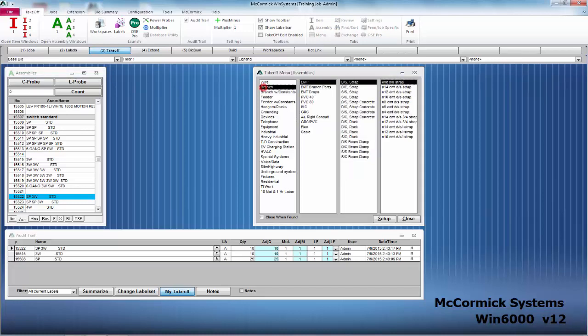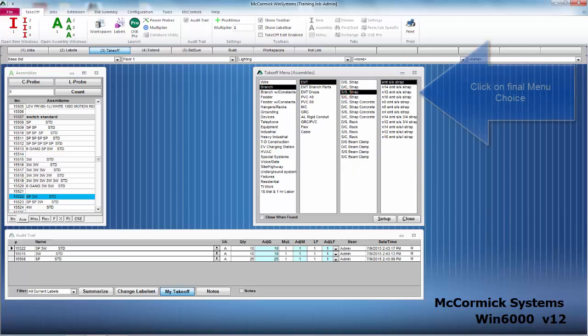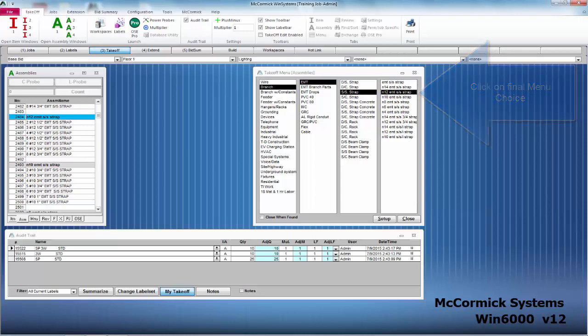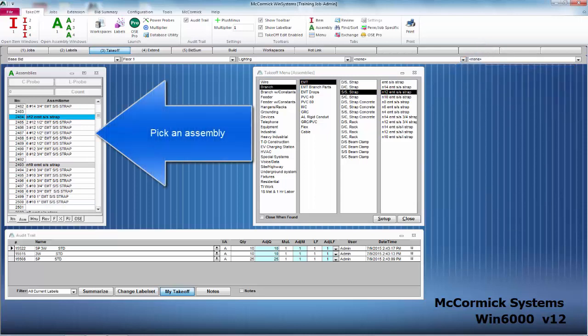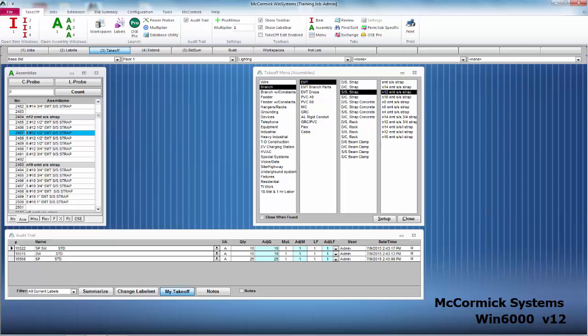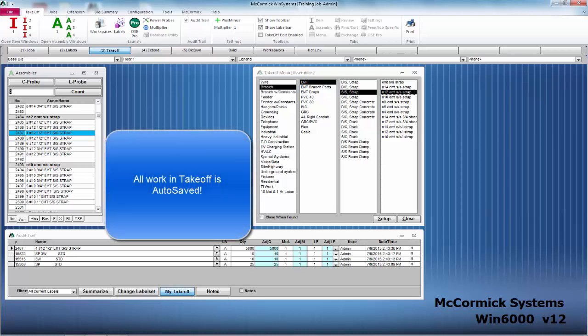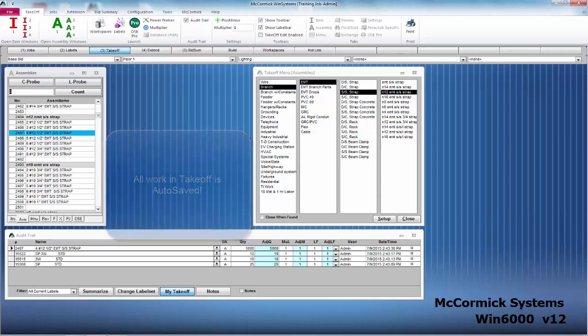Taking off lineal is the same way. We just pick what we want to take off. Let's go for some branch EMT steel set screw and we'll throw some number 12 wires in there. You'll notice in the database we can pick two number 12s, three number 12s, four number 12s. I'm going to go ahead and put in 5,000 feet of four number 12s in half inch EMT. Drop it into the audit trail and we are done. That is it for takeoff. All of our work has been auto saved. Let's go to step number four where we can get our full material list and labor report.